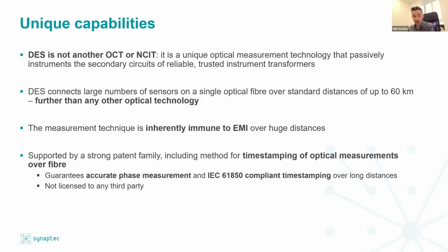Now, this patent is generic. It doesn't just apply to DES. It applies to any passive fiber optic measurement technology. And what it does is it guarantees our measurement accuracy and our compliance with industry standard communications protocols over long distances. So Synaptec can guarantee that a measurement taken with our system at 10 kilometers, at 20 kilometers, at 50 kilometers from the substation has exactly the same timestamp accuracy, phase accuracy, and communications protocol compliance as if it were taken right next to you in the substation. And that's unique to us.